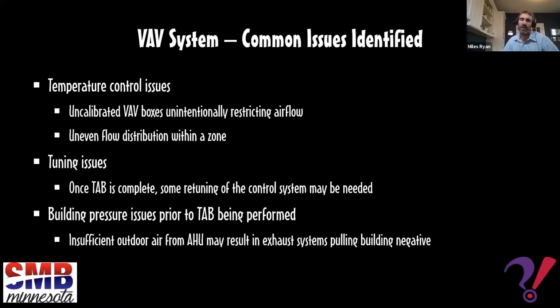So for those of you on the webinar today, this might make sense when I say I went to every exterior door in that whole entire complex and I measured how negatively pressurized that building was. And best case scenario, I found it negatively pressurized at negative 0.07 inch water gauge, and worst case scenario was negative 0.16 inch water gauge negative pressure. So had they brought in a TAB contractor when they installed all these rooftop units and set up these rooftop units to have the appropriate minimum amount of outdoor air, such building pressure issues probably would not have occurred.